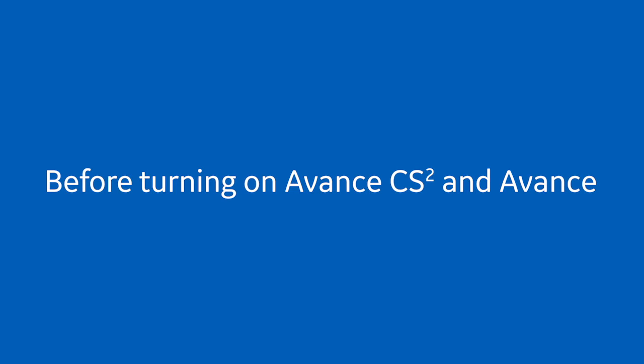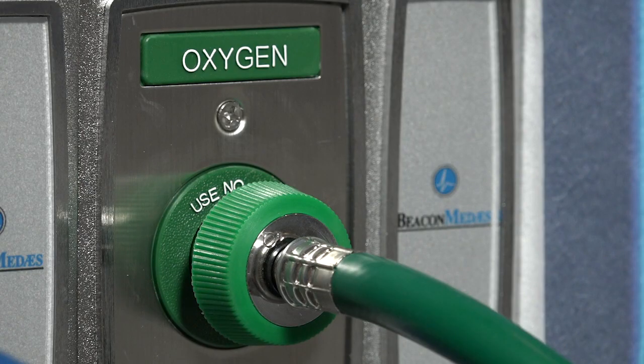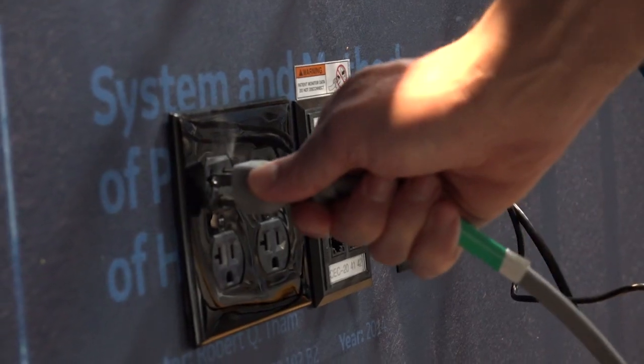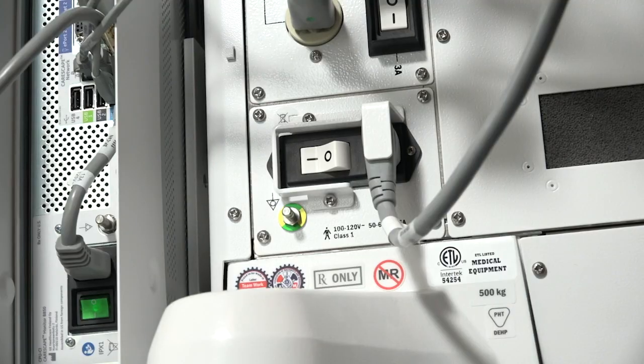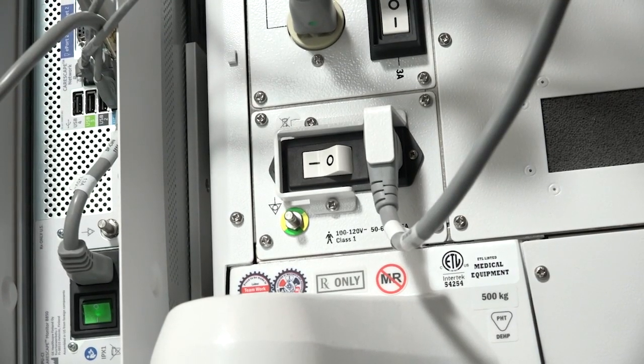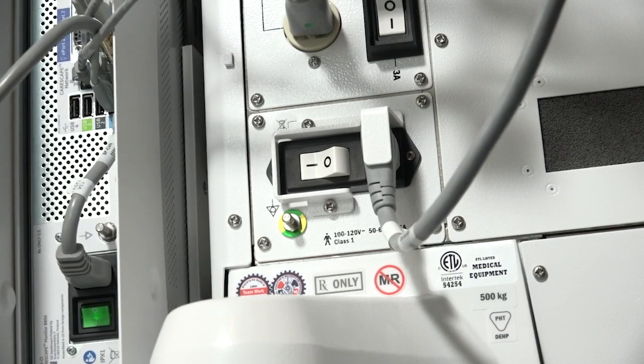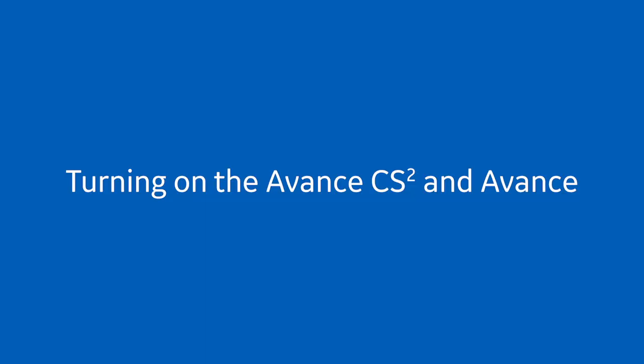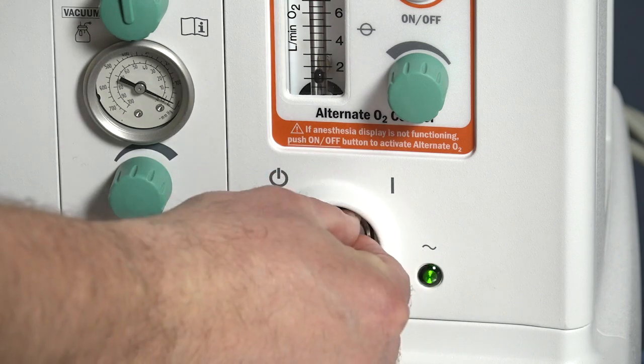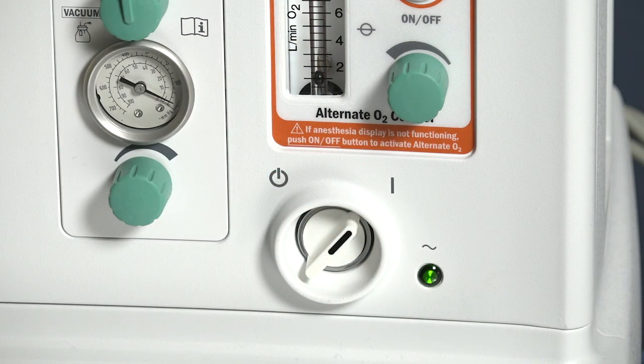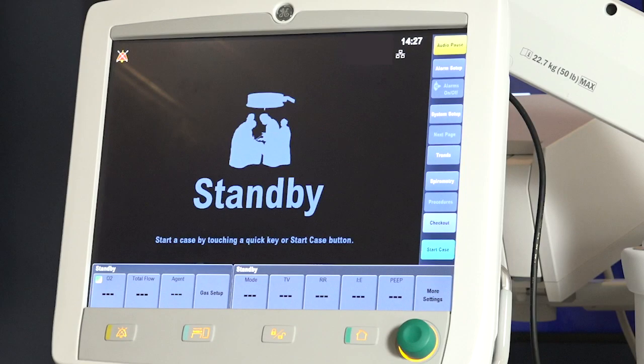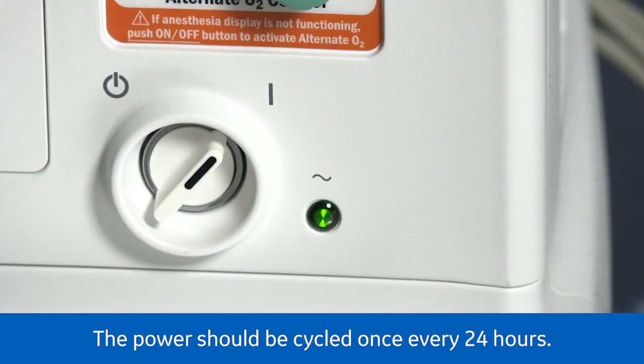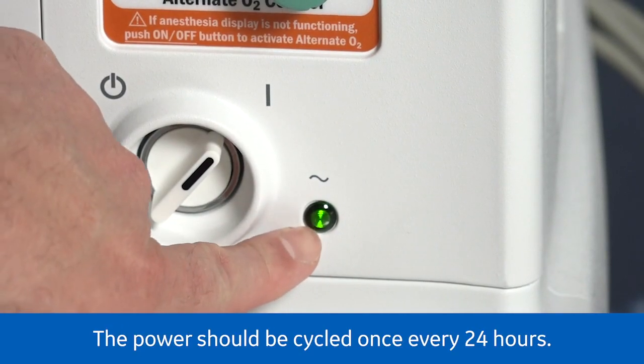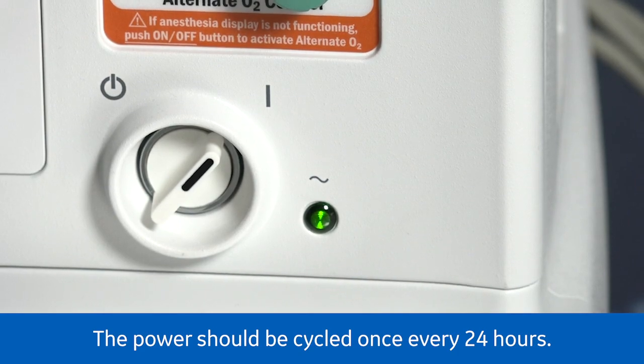For the Avance CS Squared and Avance, connect the gas supply hoses to the wall gas source or turn on the gas cylinders. Plug the power cord into an electrical outlet. Make sure the system circuit breaker located in the lower back is switched in the on position. To power the system on, move the switch from left to right to the on position. It will take approximately 45 seconds for the display screen to turn on. The green LED next to the system switch indicates there is AC power going to the system.